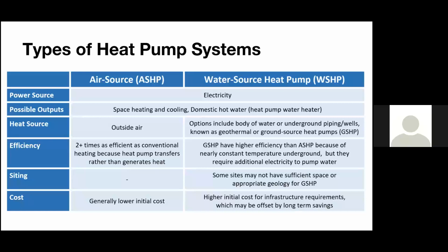Many of today's typical Boston condo buildings have water source heat pumps, but they often have a boiler in the building and a cooling tower. At some point in the summer, if everybody's water source heat pump is putting heat into the water, the loop can handle a certain amount of heat, but it'll eventually get hot, and we're going to turn on that cooling tower to cool that water down. Or in the winter, if everybody's in heating, everybody's extracting heat from the water loop, eventually the boiler will come on to moderate that water loop temperature.